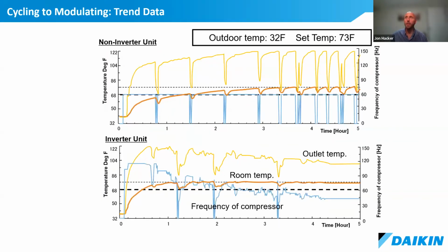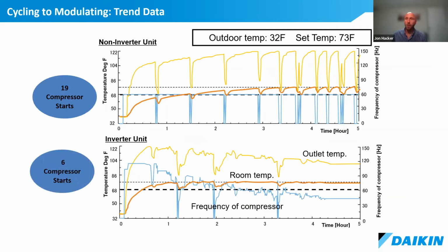So to show that more in the real world, what does that mean for the operation of the equipment? We've got 2 different examples here, and this is data that we've collected comparing a non-inverter unit on the top of the slide to an inverter product on the bottom of the slide. The color coding is pretty much the same for these 2 graphics. The yellow is the outlet temperature, the orange line is the room temperature, and the blue lines on both of these graphs are the frequency. On the left-hand y-axis is degrees, and the right-hand y-axis is hertz for the compressor frequency measurement. And I'm going to take some time to walk through this and explain what's happening.